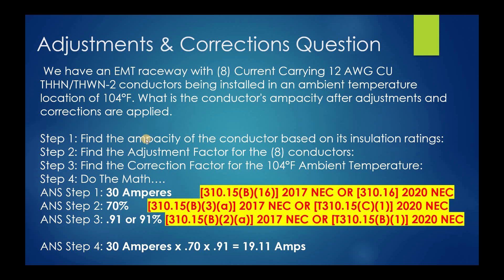It's a very simple question that comes on exams, so let's try to solve it. There are a few things we have to look for. Number one: find the ampacity of the conductor based on its insulation rating. Next, find the adjustment factor for those eight current-carrying conductors. Then find the correction factor for the ambient temperature, since it's other than what's given in the ampacity tables. Finally, we just do the math.